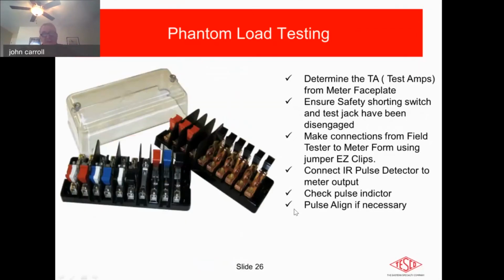There's our test switches that we use. These are very familiar to most people, I'm sure. We don't need to go through a lot of detail, but suffice to say, you can clearly get access to these through the cover and the cover off. This is the one that's a shorting switch, that's your shunt. So if you operate this and it comes down this way as you open it, that basically shorts out the CT, opens it up. So you've shunted the CT out. So there's no current coming to the meter, but it's still operating.